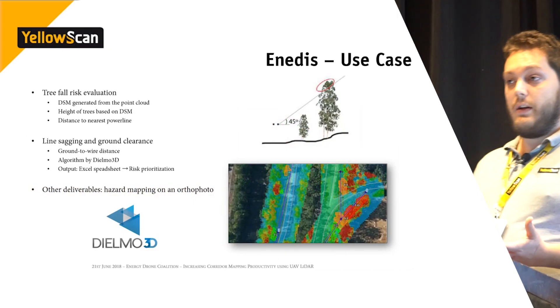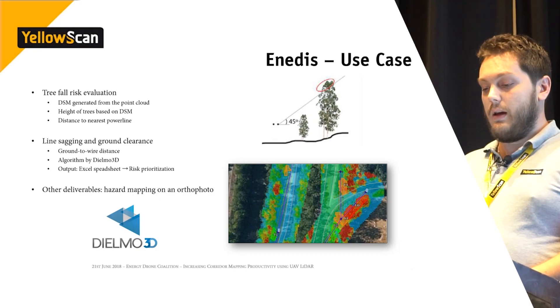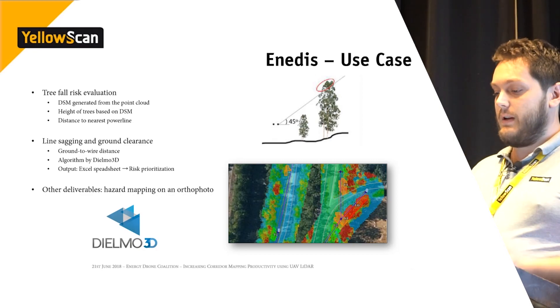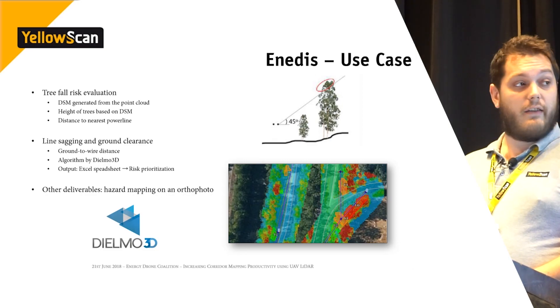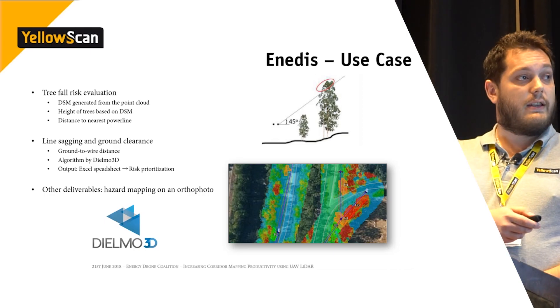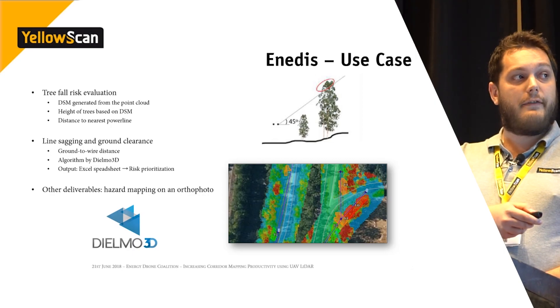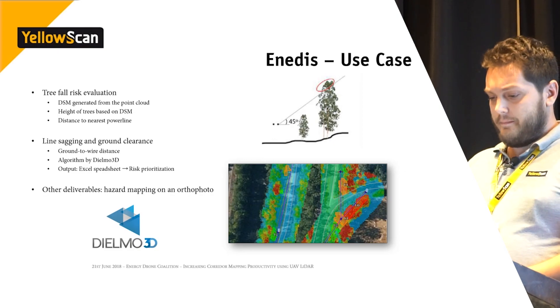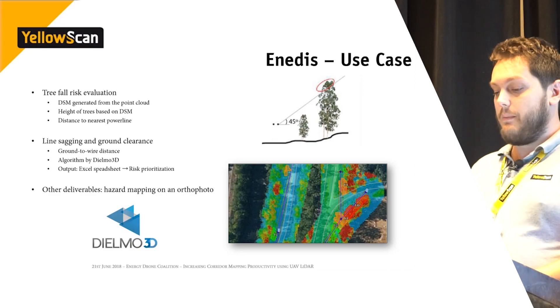The second result is a tree fall risk evaluation. Based on the classified point cloud, they generate a DTM (digital terrain model) and a DSM (digital surface model). From these they get the height of each tree and, based on the power line location, can easily determine if a tree would fall on the power line in a worst-case scenario — making it easy to define pruning priorities.